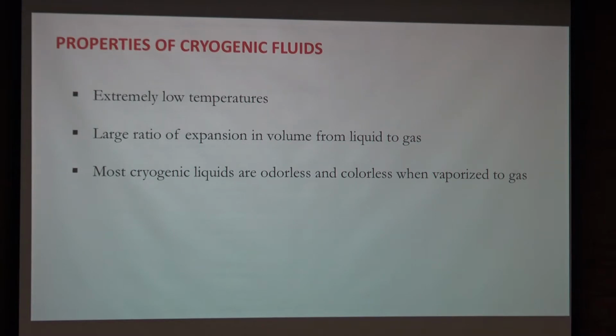And one thing that applies to all of these liquids is that they're going to expand as they heat up. When the liquid evaporates, and they're always close to their boiling points, you will find that they expand quite dramatically in volume. And that can displace air and cause an asphyxiation hazard. Most of these liquids are colorless and odorless, and you don't really notice their presence except for the fact that they will displace oxygen and create an asphyxiation hazard.